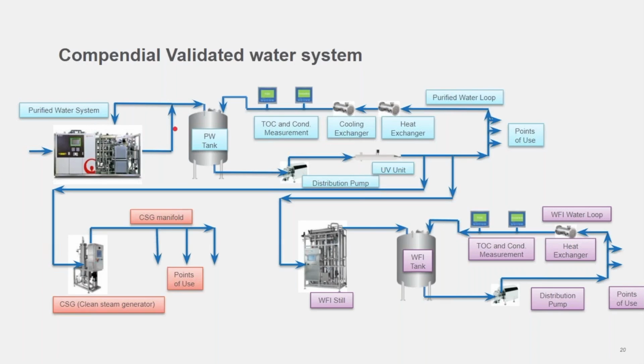I remember going a number of years ago to a site in Denmark where we asked the customer, what's the cost to you if the water treatment system is not running? And they've obviously done their homework, and one of the guys piped up and said 16,000 euros per minute is the loss to them if that water treatment system is not running. So that's almost just under €1 million an hour.